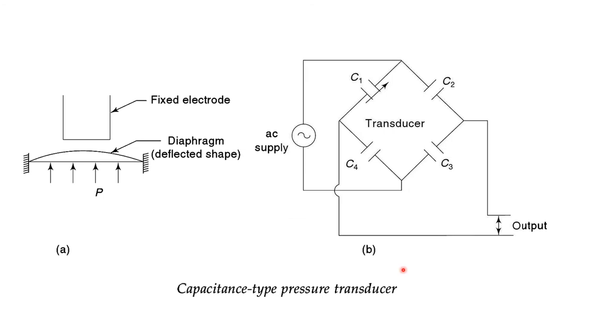We can also have a capacitive-type pressure transducer. Here a diaphragm is present; when pressure is applied, the gap reduces, which in turn changes the capacitance of the capacitor. This capacitor is attached to a Wheatstone bridge, so the change in capacitance disturbs the bridge. The voltage required to re-balance the Wheatstone bridge indicates how much the capacitance has changed, and from the change in capacitance we can calculate the applied pressure.